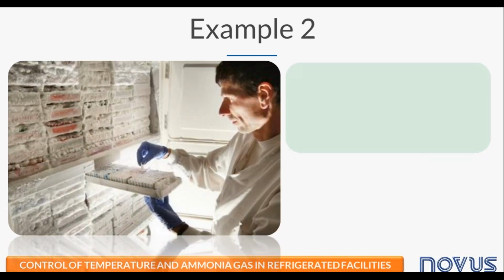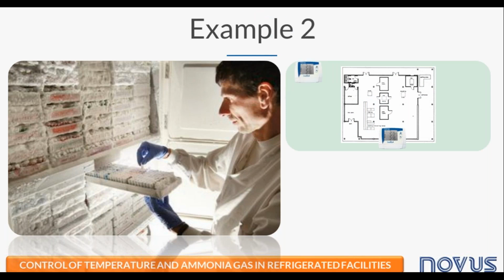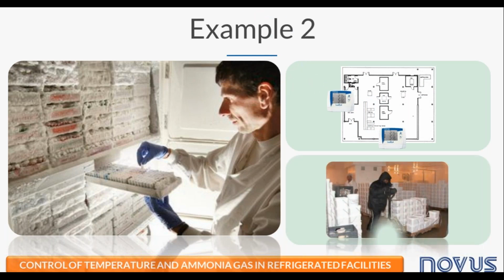A second example is the control of temperature limits and ammonia gas in refrigerator facilities. The analysis of the infrastructure blueprint defines, for example, 2 critical points of monitoring. Using an ammonia gas leak detector, let's say it is a digital sensor and can be set as alarm. The high limit of temperature may also be set to trigger the buzzer alarm. Because of the memory capability of LogBox, the user may promptly define weekly data download for getting history profile of temperature. Those log files may be stored in the computer or file servers and be used in future audits or for report issuance.